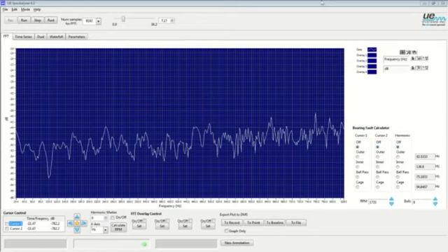And that does seem to be the trick, and I do not want to oversimplify what we're going to talk about today, but if you break down and characterize the type of faults that we're looking for in electrical systems, there's really 5 or 6 that are present, and you're familiar with the majority of them being arcing, tracking, corona, mechanical looseness, vibration, and contact chatter.